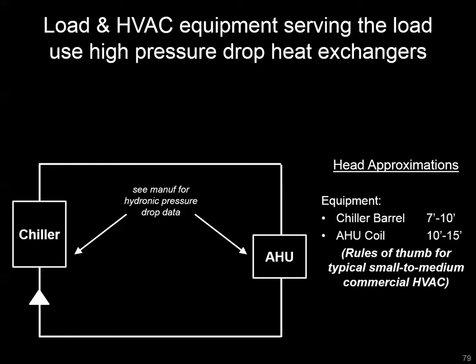The first thing we start with is those heat exchanger devices, and those are typically high pressure drop because of the surface area and the coils and passes included in some of these devices. You're trying to get as much time and space against these working fluids in this indirect heat exchange, and that is going to cause additional pressure drop relative to other components. There is published manufacturer data about what a typical air handling unit coil or chiller evaporator barrel pressure drops are going to be at different flows and conditions, but there are rules of thumb we can use for initial determination.